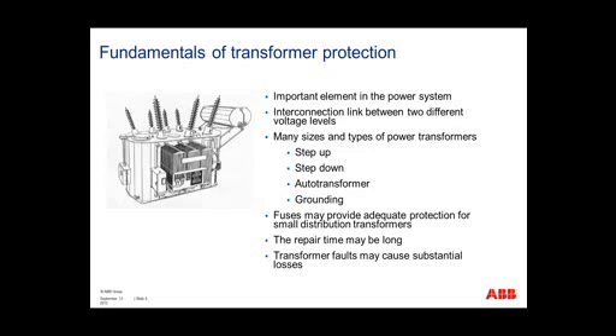Different methods of protection could be fuses. These provide adequate protection for small distribution transformers. Typically, you won't see fuses in large transformers because of just the nature of the fuse. Fuses require a large amount of current to actually blow, and sometimes they allow a large amount of current to actually damage the transformer.